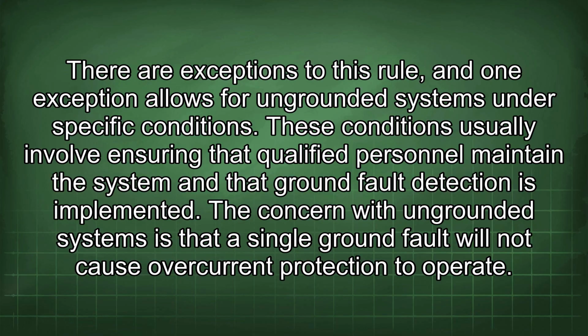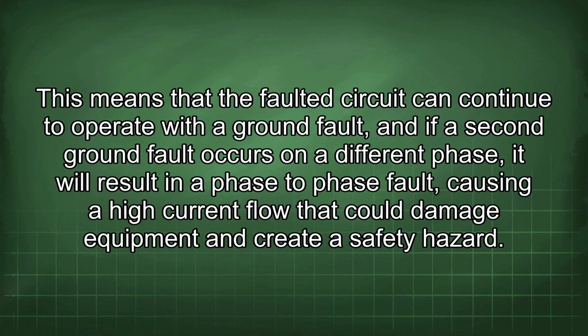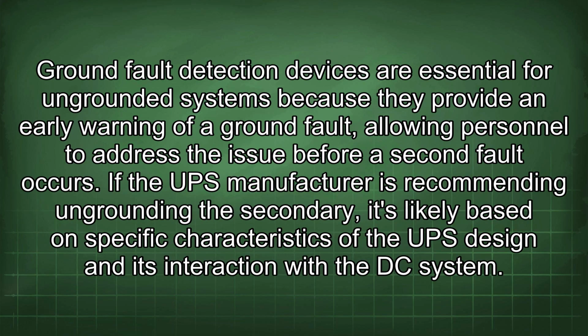The concern with ungrounded systems is that a single ground fault will not cause overcurrent protection to operate. This means that the faulted circuit can continue to operate with a ground fault, and if a second ground fault occurs on a different phase, it will result in a phase-to-phase fault, causing a high current flow that could damage equipment and create a safety hazard. Ground fault detection devices are essential for ungrounded systems because they provide an early warning of a ground fault, allowing personnel to address the issue before a second fault occurs.